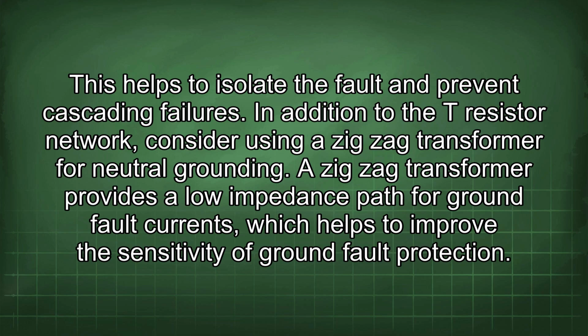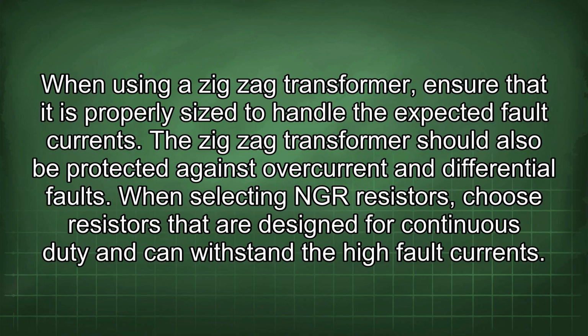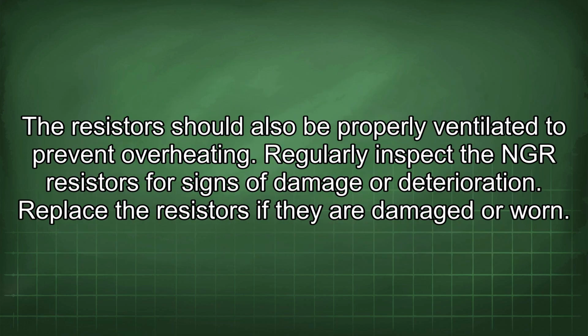In addition to the T resistor network, consider using a zigzag transformer for neutral grounding. A zigzag transformer provides a low impedance path for ground fault currents, which helps to improve the sensitivity of ground fault protection. When using a zigzag transformer, ensure that it is properly sized to handle the expected fault currents. The zigzag transformer should also be protected against overcurrent and differential faults. When selecting NGR resistors, choose resistors that are designed for continuous duty and can withstand the high fault currents. The resistors should also be properly ventilated to prevent overheating.